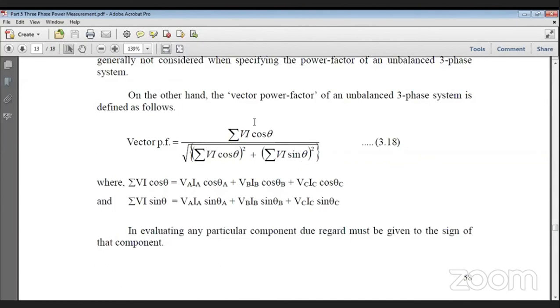So if I am the industry, I cannot contest this calculation. So what the power company has now installed is called a vector power factor meter. They never install 3 different meters like this. These meters calculate 3 different phase powers as well as 3 different reactive powers, and then calculate this one. And accordingly, all the calculation of power and its charges, etc., are done.